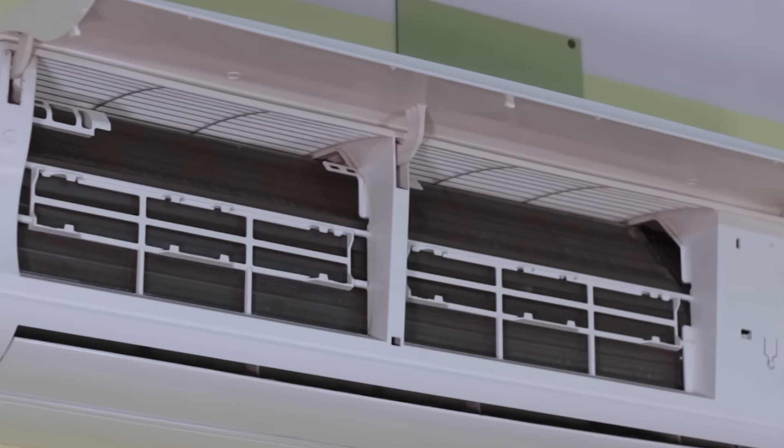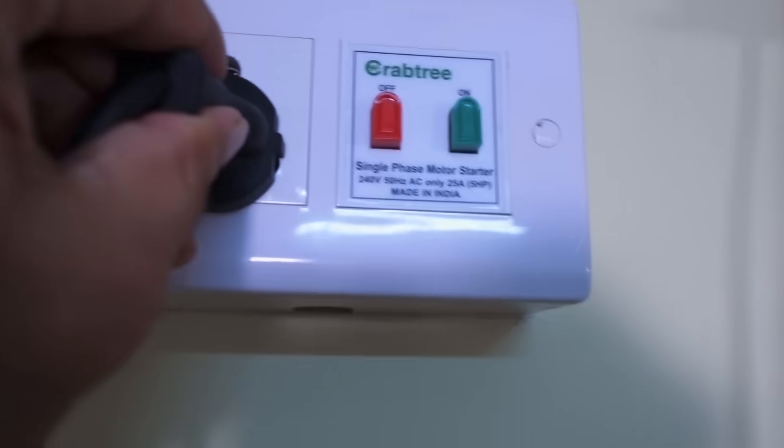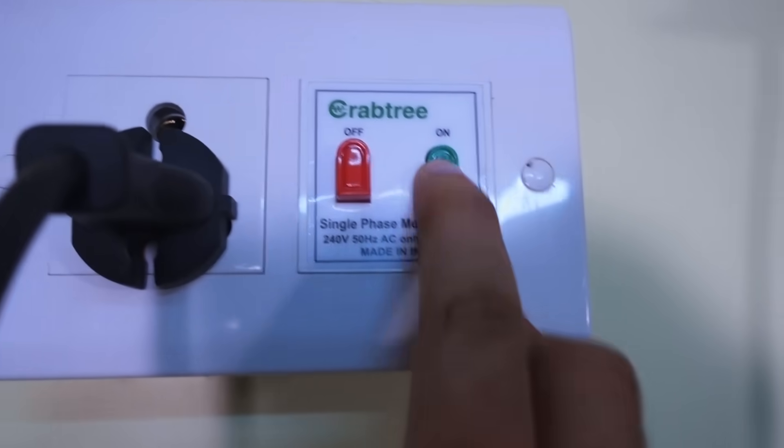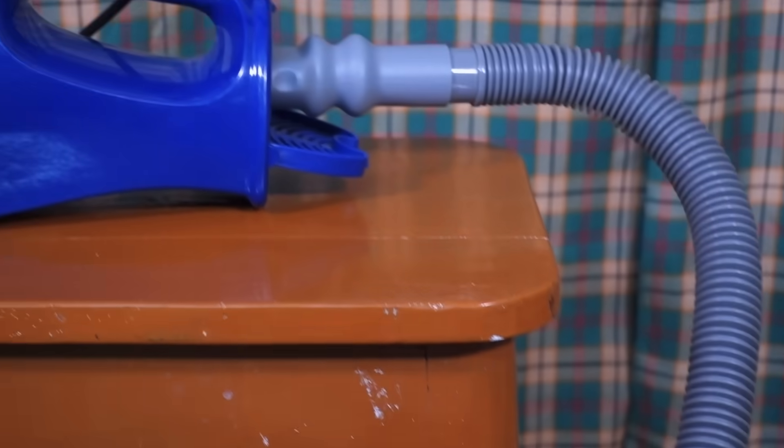After removing air filters you will notice that AC fins are blocked with insane amount of dust. To remove those dust you can use an air blower or an air compressor. I am going to use an air blower. Turn the air blower on and move the air blower head vertically and make sure blower head doesn't touch the AC fin.